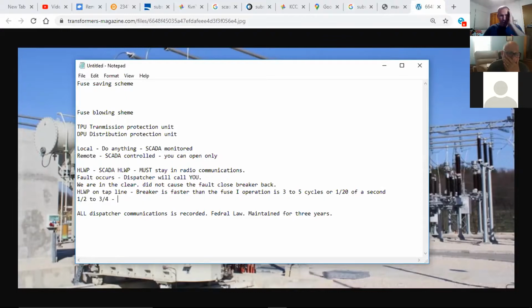Big difference when you talk about exposure. Yeah, exactly, that exposure to voltage is something that's going to kill you anyway if there's electrical current traveling through your body. But if you can limit exposure to the arc flash and flame to 1/20th of a second instead of half to 3/4, guys, that's monumental as far as the damage that's going to happen to the equipment, the pole, or to you. So that's why we get hotline work permits on tap lines.